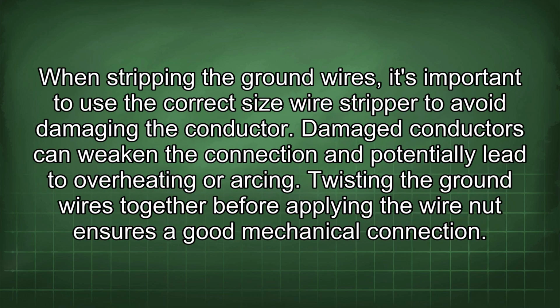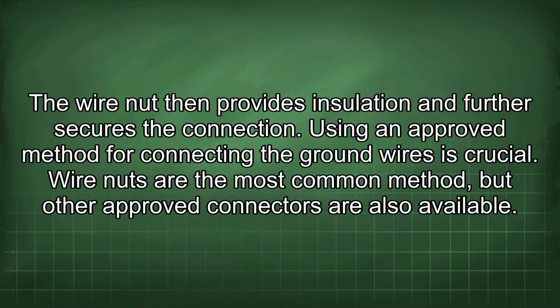When stripping the ground wires, it's important to use the correct size wire stripper to avoid damaging the conductor. Damaged conductors can weaken the connection and potentially lead to overheating or arcing. Twisting the ground wires together before applying the wire nut ensures a good mechanical connection. The wire nut then provides insulation and further secures the connection. Using an approved method for connecting the ground wires is crucial. Wire nuts are the most common method, but other approved connectors are also available.